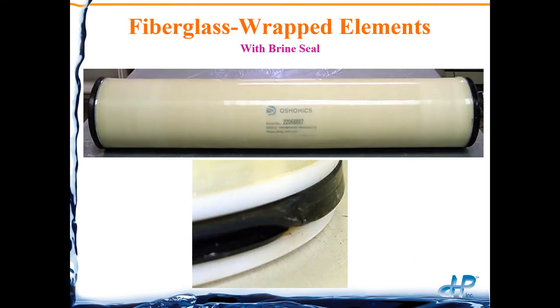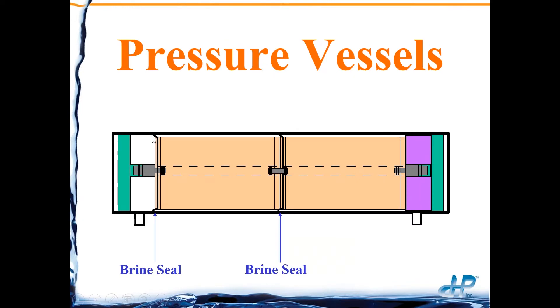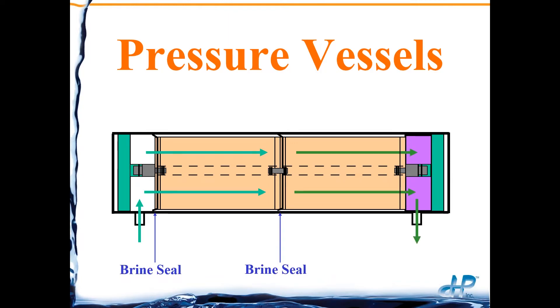Membrane elements for most industrial applications are fiberglass wrapped, and all RO membrane elements look essentially the same regardless of manufacturer. On the feed end of each fiberglass-wrapped membrane element, there's a brine seal. This brine seal doesn't allow feed water to go on the outside of the membrane element, forcing the feed water to go through the membrane element and then exit.